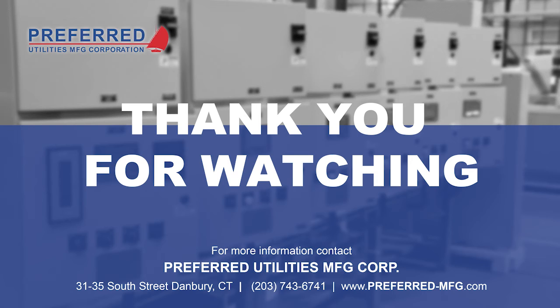Now, if a return pump is energized, an alarm's going to be energized too, because the return pumps come on at 90% and our pump off level is at 80%. So the oil should never get up to 90% in a normal condition. So we're going to be sounding the alarms anyway.